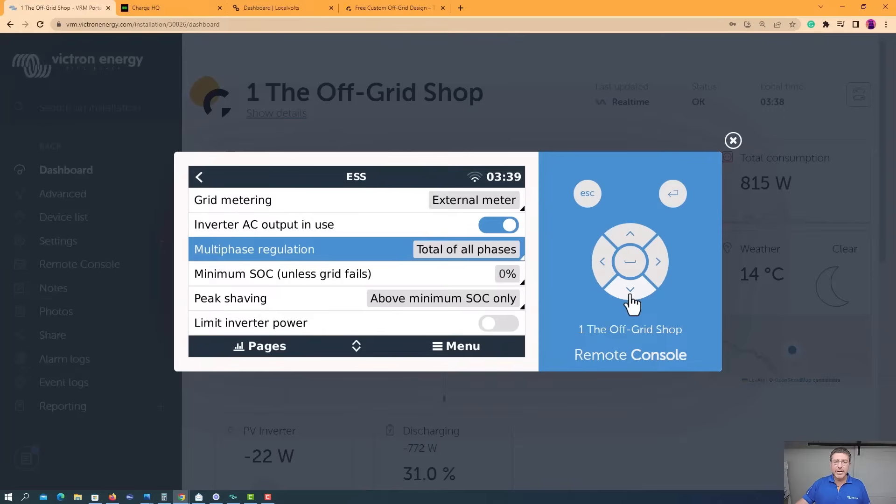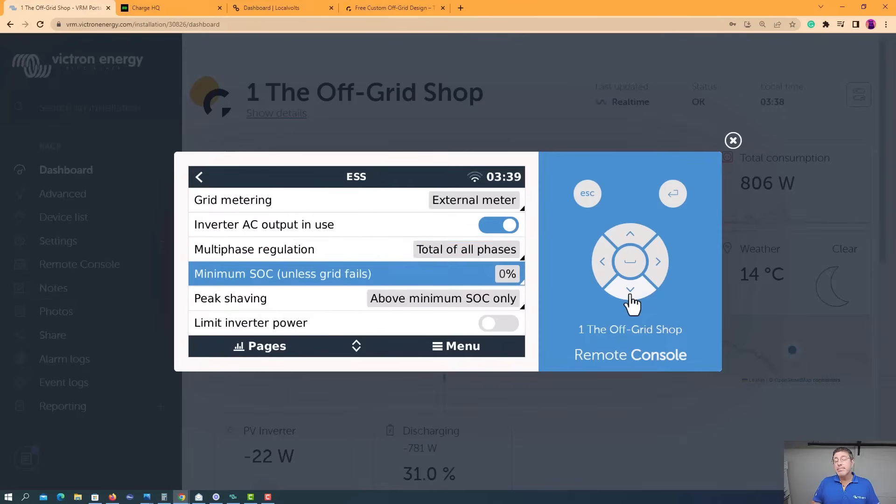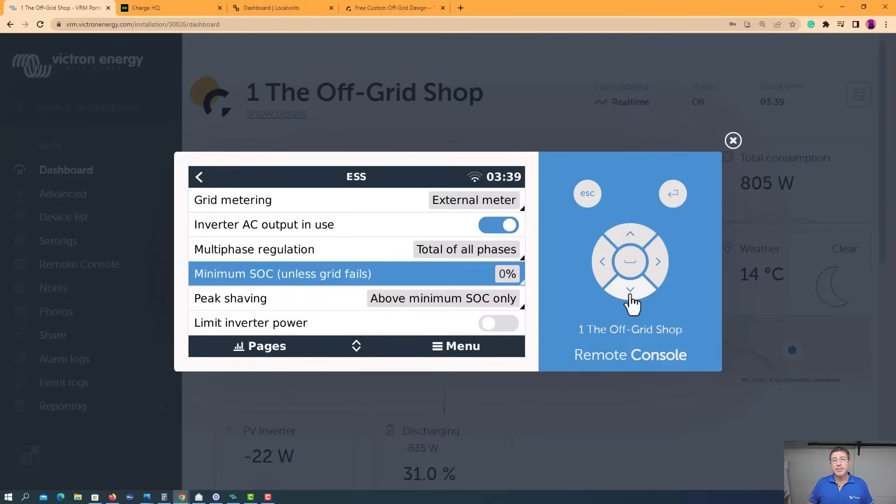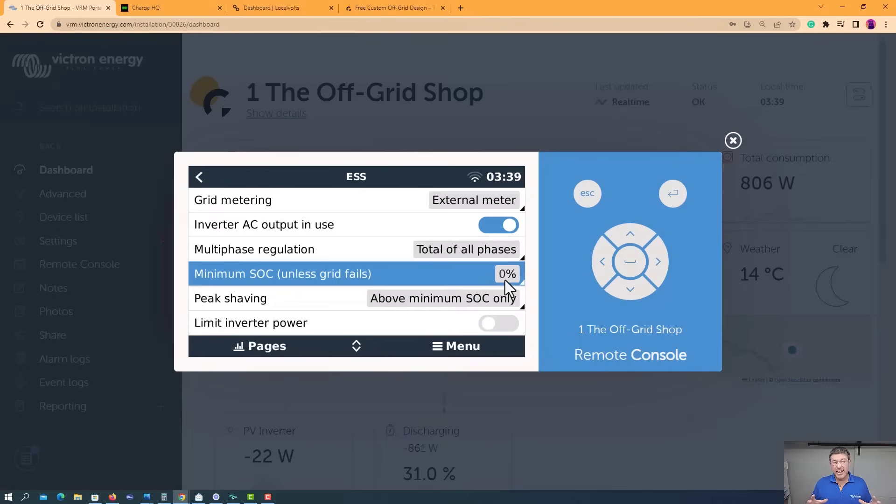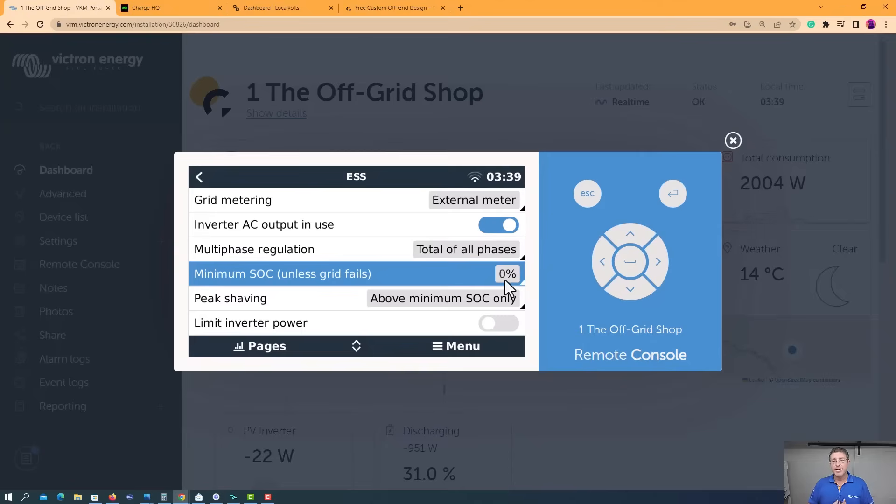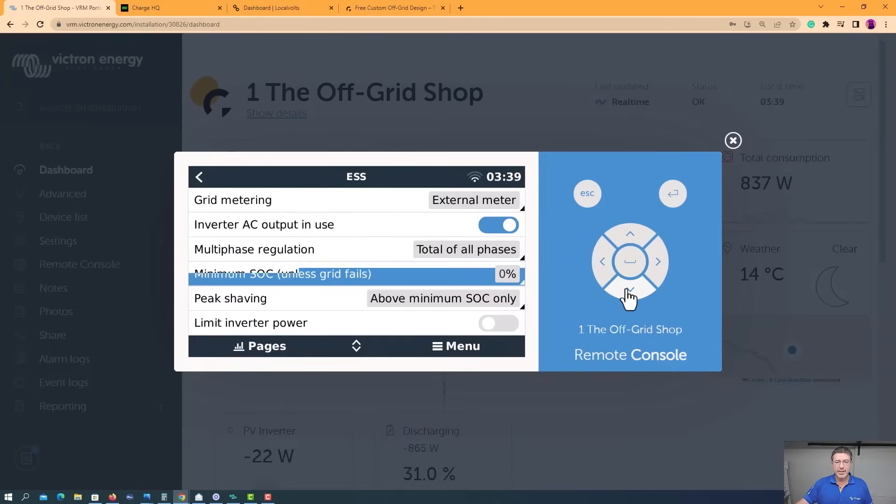Before we're going to show you a quick setting, I'm turning my batteries on to keep batteries charged. I'm just going to quickly shut that down so you can actually see. As you see from the grid here, my system starts pulling from the grid. So when you hit this setting on, it's actually going to start charging your batteries straight away and it's going to get them to whatever you got set as a setpoint to keep those batteries topped up. Now when we come back here to our remote console, I'll come back here and I'll turn that off, back down to optimize without battery life. I'll show you a few other settings and scheduled charging and how I use it and how it can be useful.